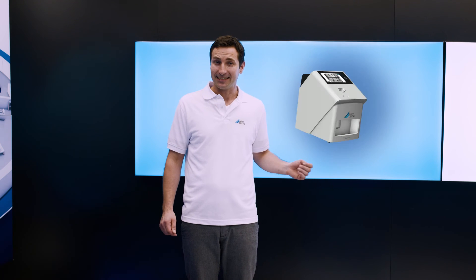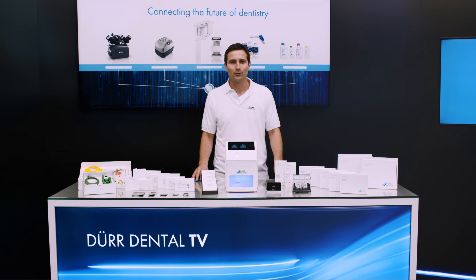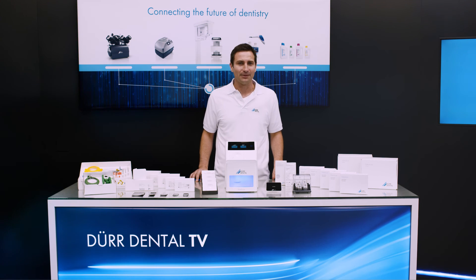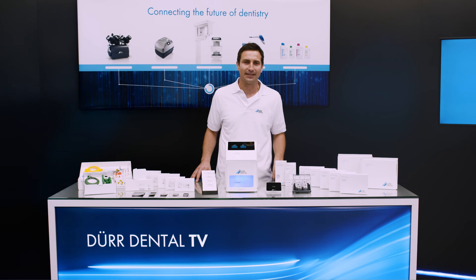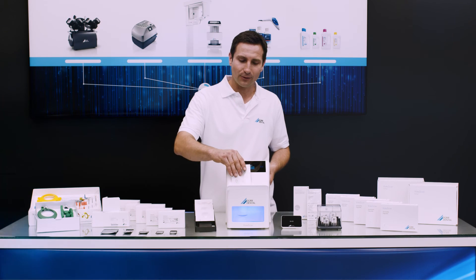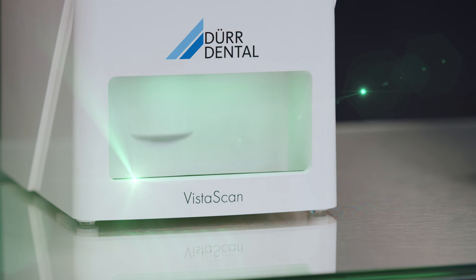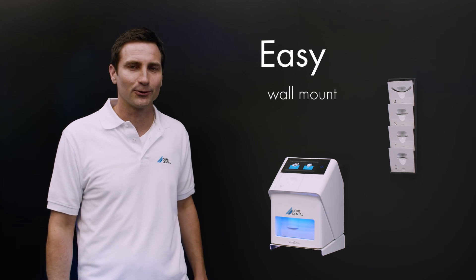VistaScan MiniView 2.0 — the most intelligent Mini there has ever been. An extensive set of supplied accessories ensures a smooth start and effective operation from the very first day. Since VistaScan MiniView 2.0 is able to digitize image plates in all intraoral sizes, image plates and light protection covers are also available in sizes S0 to S4. To change the image plate format to be scanned, simply change the loading insert — a really easy process. The color of the ambient light can be matched to the interior decor of your practice, and if you're short on space, VistaScan MiniView 2.0 can also be wall-mounted.